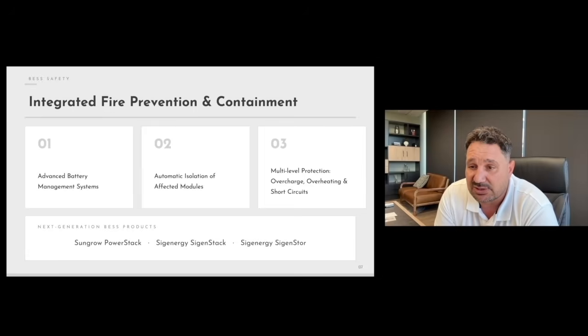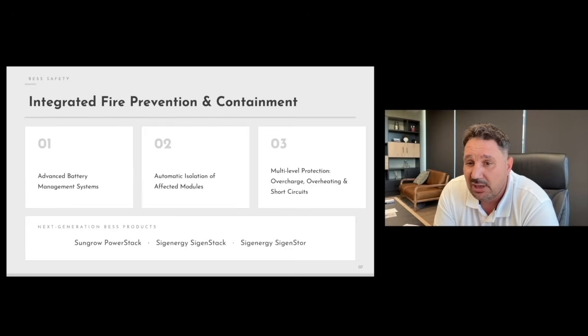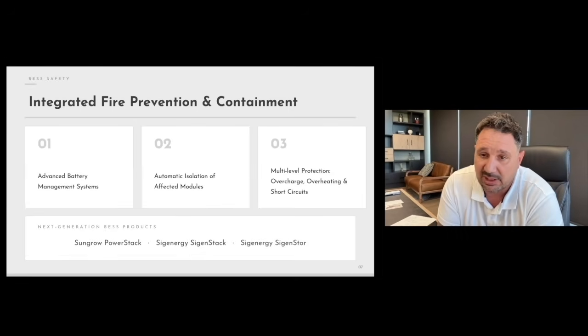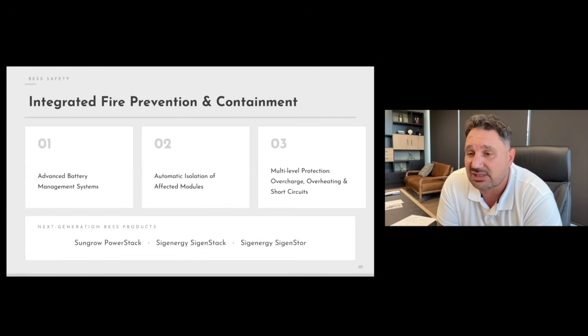These include advanced battery management systems for continuous temperature and fault monitoring, automatic isolation of affected modules, and multi-level protection against overcharge, overheating, and short circuits, all of the culprits that Anthony did speak about. And in certain systems, additional safety features such as integrated fire detection and suppression are also included. These further strengthen the overall system resilience. Sungrow's power stack utilizes a multi-layered protection strategy to mitigate thermal runaway and electrical risks. Key safety features include intelligent liquid cooling, advanced cell level monitoring, and integrated fire suppression systems. These capabilities enable early detection of abnormal conditions and help prevent the escalation or spread of fire-related incidents.